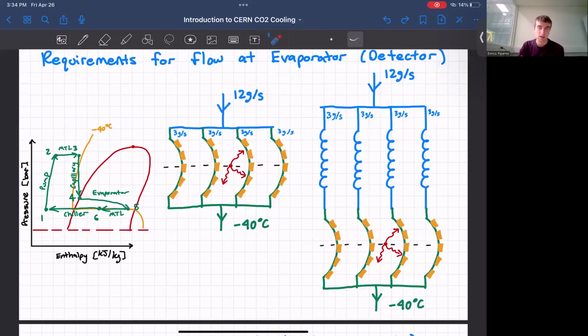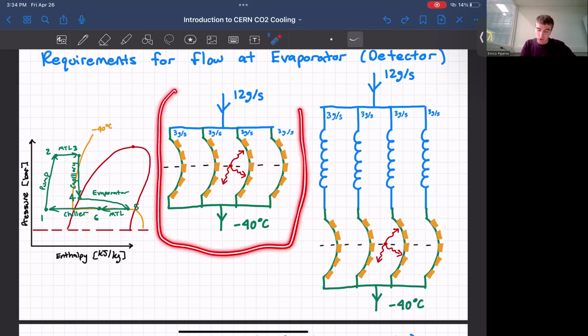On this slide, we will discuss another requirement for flow of the evaporators, which is the capillaries. The capillaries have two main functions in the detector. The first is to distribute the flow to the tight areas in the evaporators, and the second is as a fail-safe to protect evaporators in case subsequent evaporators break, which we'll be discussing shortly. Here I drew the beam path along which the protons collide, and the evaporators form a cylinder along this beam path in order to measure trajectories of charged particles in all directions. The evaporators might be a semicircle, and there's another semicircle on the other side to close the loop. So the flow is usually distributed in parallel to multiple evaporators.